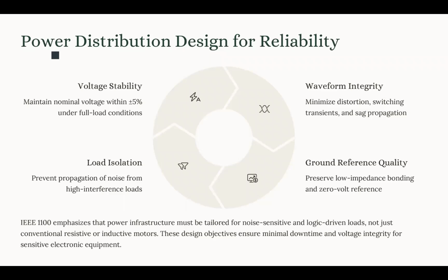We have the ground reference quality as another aspect of the power distribution, another point that we need to keep in mind when we're designing the power distribution system. The recommended design criteria is, for example, maintaining a low impedance bonding and keeping the common mode voltage under the defined threshold. We have another aspect that we need in our power distribution, which is load isolation. So basically, the loads in our system should be physically and electrically separated. There are some definitions for the zones in our system. So we could have inductive loads or nonlinear loads. All these are defined, and we have to segregate them. So the loads should be isolated from each other.